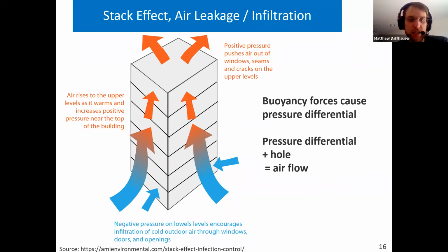On a cold winter day, a typical residential building may lose an entire volume's worth of air over 2 hours, and this effect gets stronger the colder it gets. This effect is significant and it is responsible for about half of peak heating load.